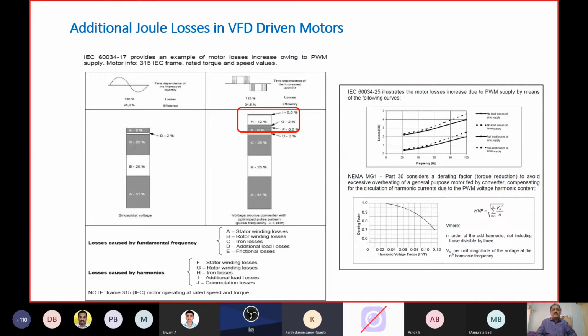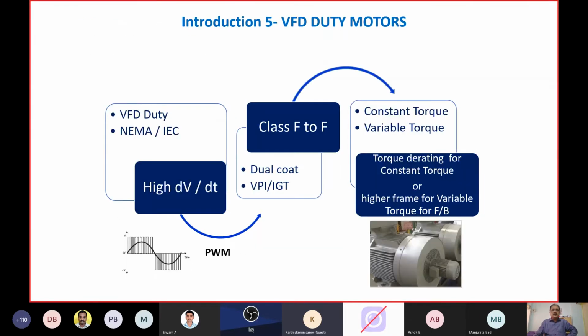But the fact remains that when driven through a VFD, due to the PWM wave, there will be additional losses in the motors. The motor's own efficiency will come down slightly, but the overall efficiency saving, which we saw in the last two slides, two-digit savings, is available through efficiency improvement in the system, by cumulative system optimization.